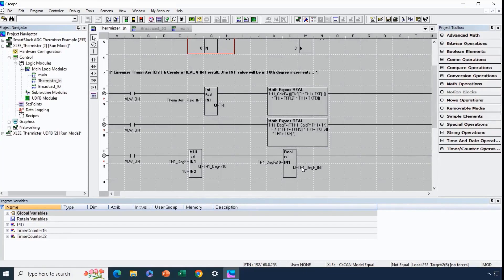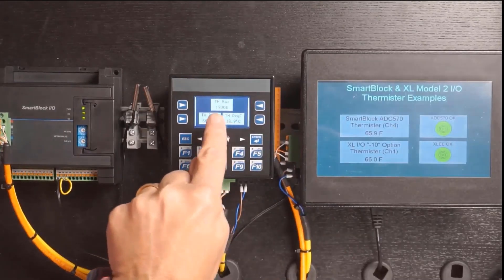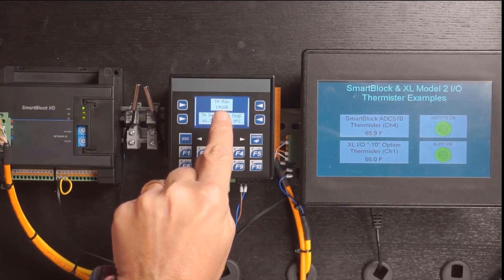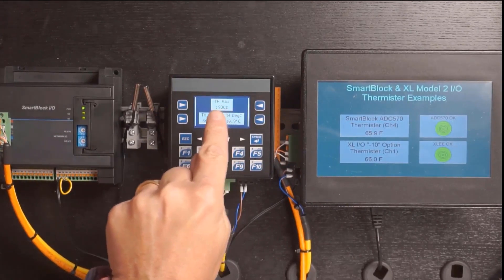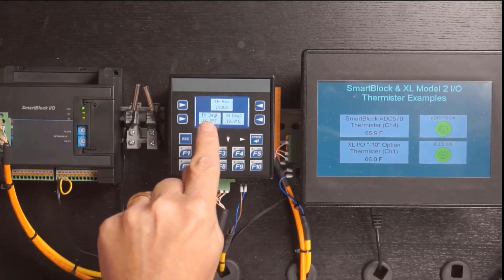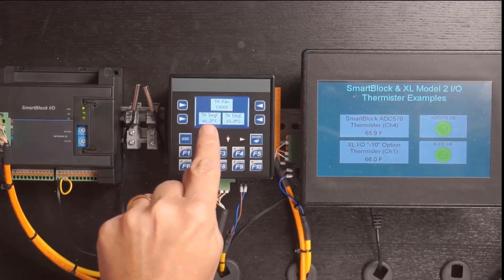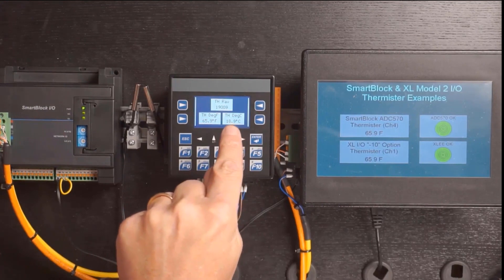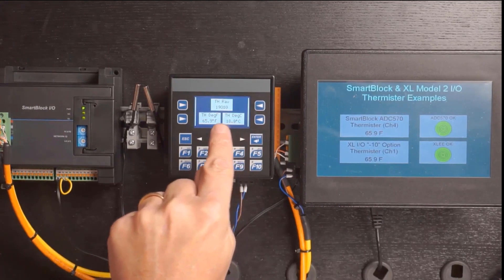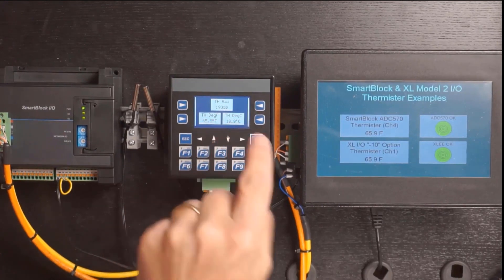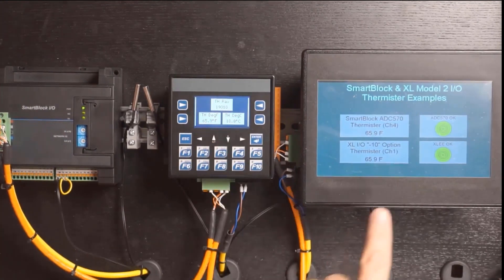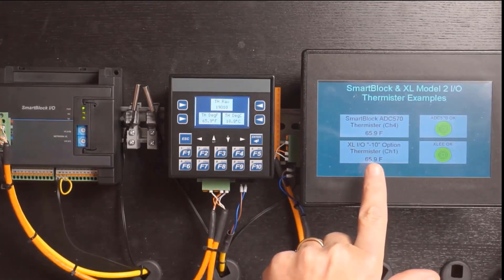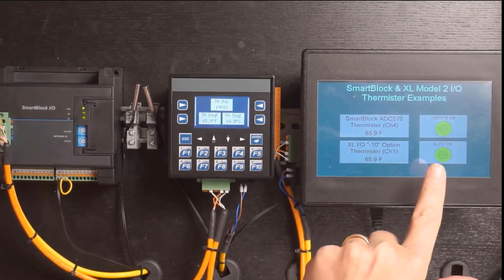The raw value coming in from the AI is about 19,000 counts, and after running it through the equation with those coefficients, we ended up with approximately 66 degrees Fahrenheit, which correlates to 18.9 degrees Celsius. That's what's involved in the XLE on a channel-by-channel basis for every channel using thermistor. You'll also notice that we have the XLE's thermistor value being displayed, as well as an OK indicator for that controller.